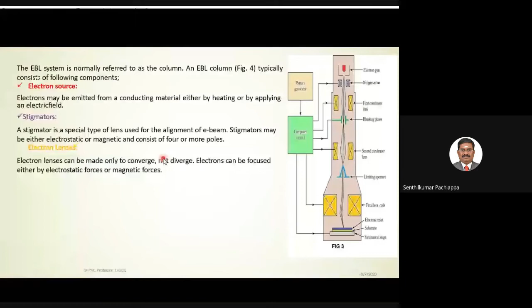Electron lenses. Electron lenses can be made only to converge, not diverge. So electrons can be focused by either electrostatic force or magnetic force. Apertures. Apertures are small holes through which the beam passes on its way down the column. There are several types of apertures. A blanking aperture is used to turn the beam on and off. A beam limiting aperture has two effects. It sets the beam convergence and the angle through which the electrons can pass through the system, controlling the lens aberration and thus the resolution.